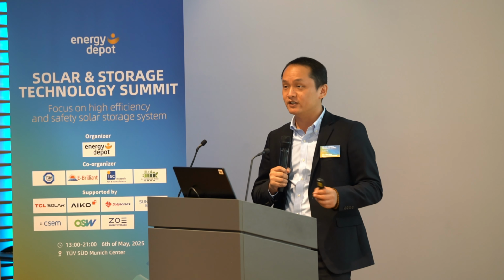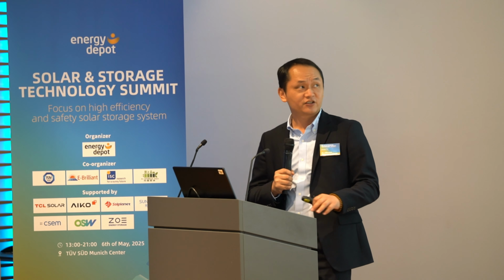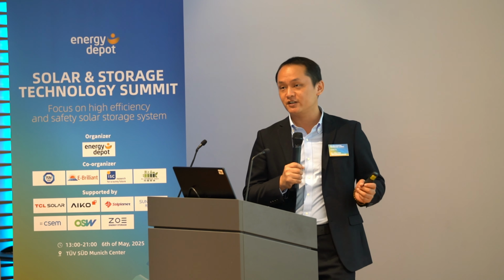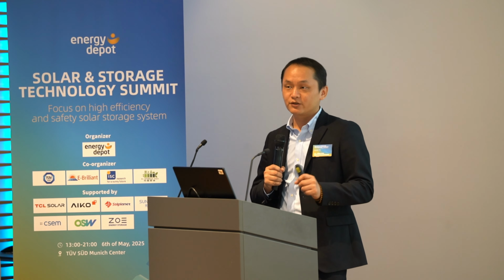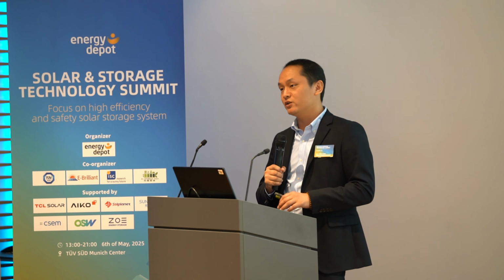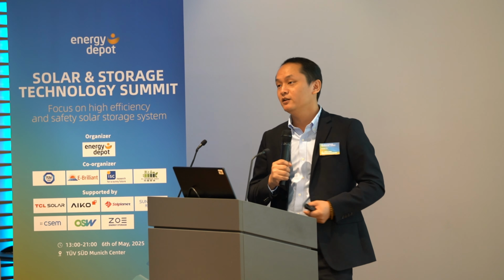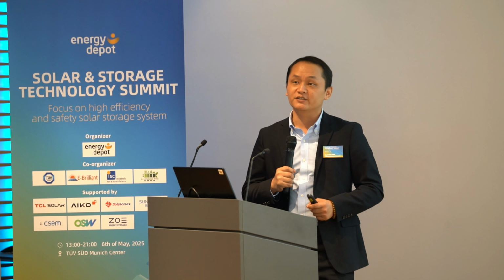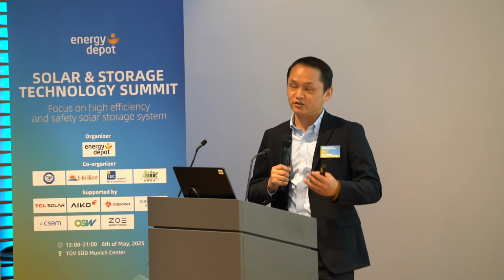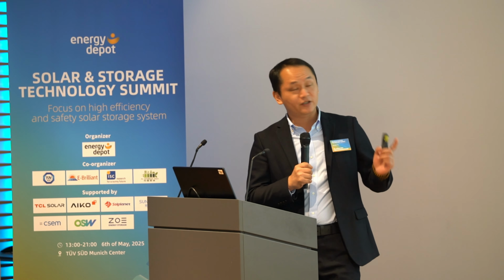In the first stage, we have cell temperature sensing, and also pack level flammable gas sensing. If anything is wrong, we will stop the system and use Novec 1230 or FK-5-1-12 to cool it down. But now that material is forbidden, so we are going to change to some other material or get rid of this process.